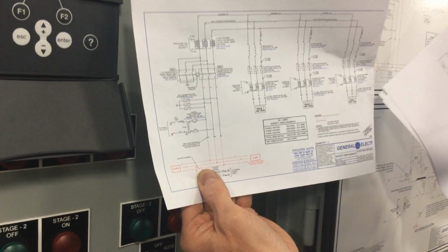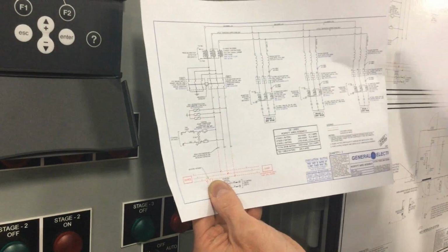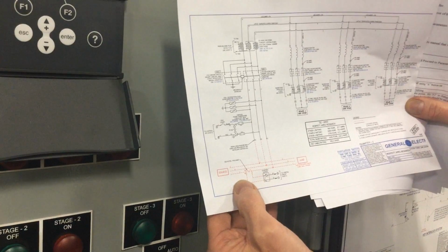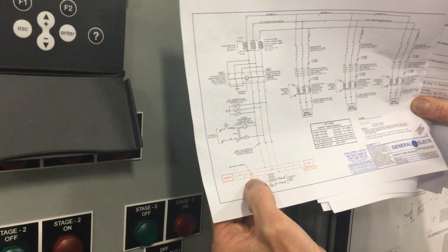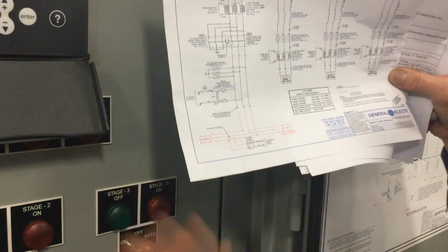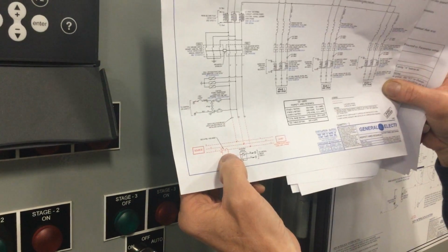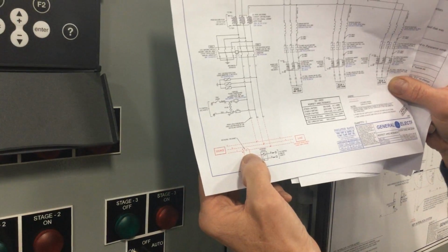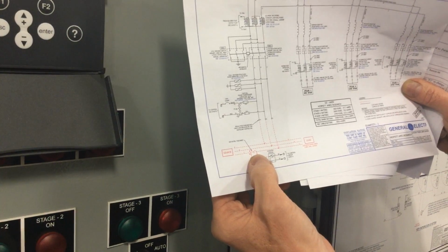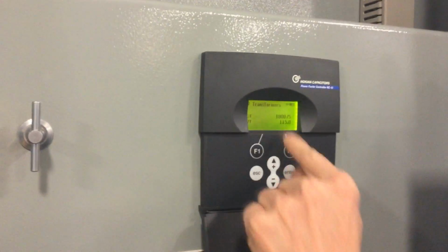So this needs to see all the current, all the load that you're trying to correct, including the capacitors. So placement of the CT is very important in order to get correct readings. These are generally placed by contractors who are installing the switchgear or setting up the capacitor bank. And we need to know the value of that CT. It's usually on a one-line diagram, or the installer, if they're available, can tell you what value that CT is set for. And that value needs to go into here under CT.